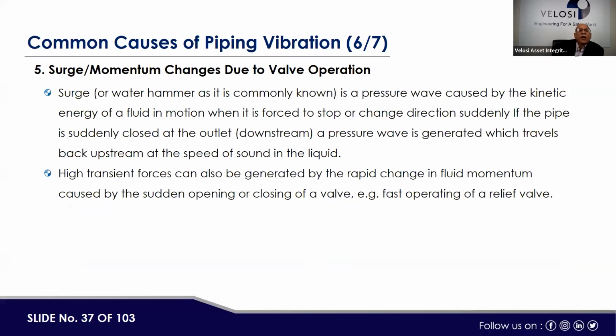Now, surge: momentum change due to valve operation. A surge is a pressure wave caused by the kinetic energy of a fluid in motion when it is forced to stop or change direction suddenly. For example, if an outlet valve is closed, there could be a backflow and surge which can impact backward, and it may also cause a sudden failure, high vibration and high sound as well. High transient forces can also be generated by a rapid change in fluid momentum caused by the sudden opening or closing of valves, for example, fast opening of relief valves.